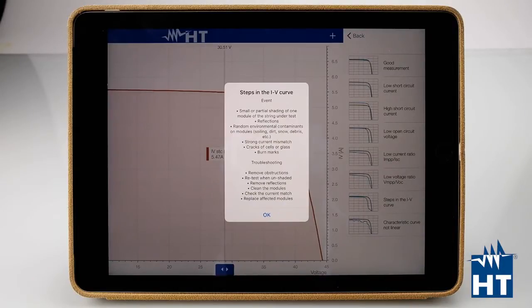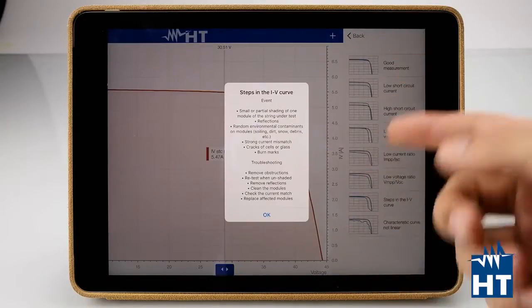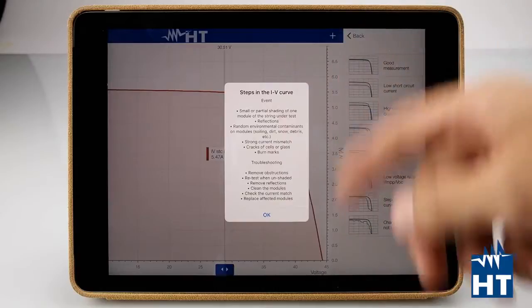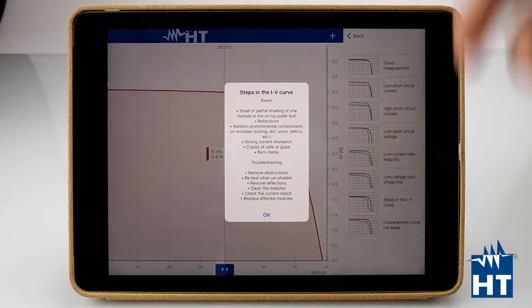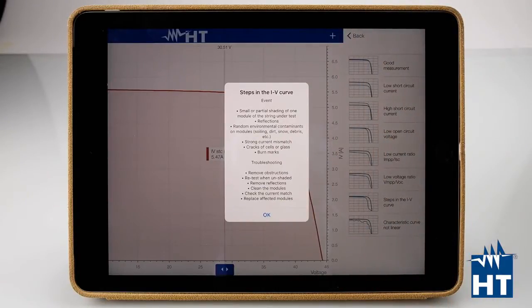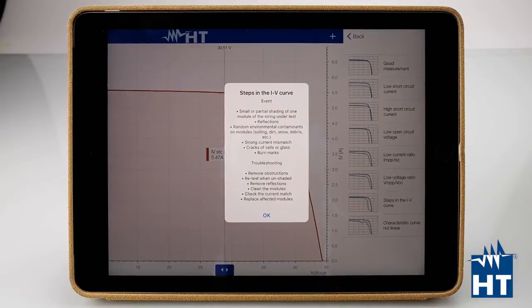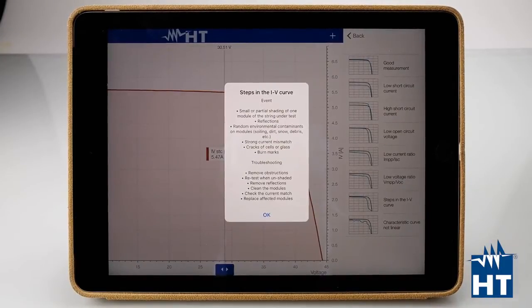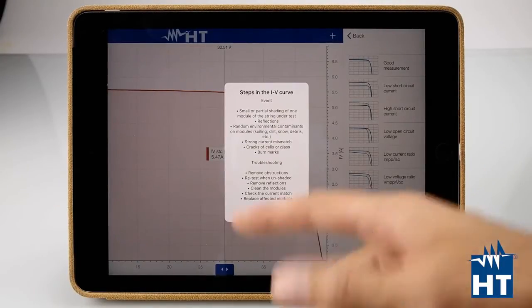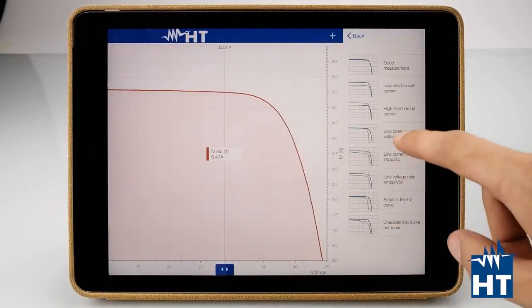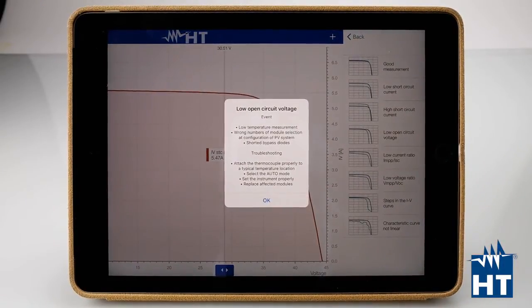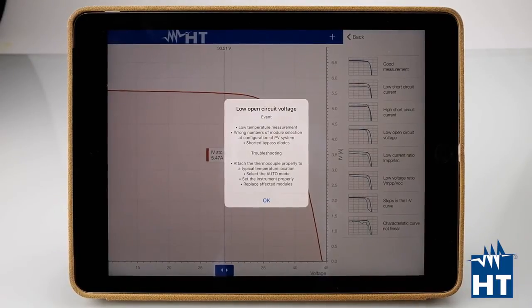Small or partial shading of one module of the string under test, reflections, random environmental contaminants like dirt or snow. Strong current mismatch or cracks or cell burn marks. With the wiki you can find the more common problems and it will be very easy to find your solution.